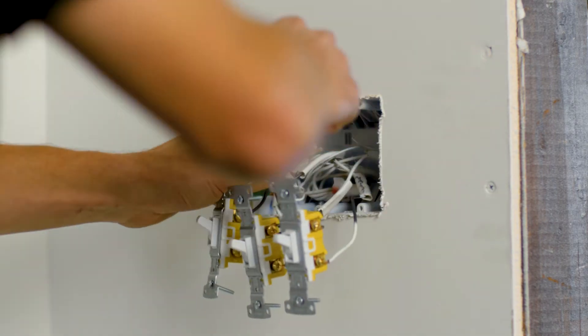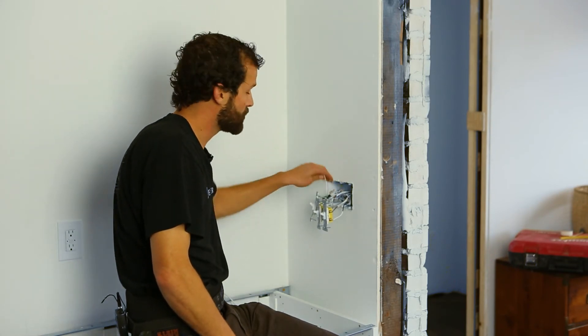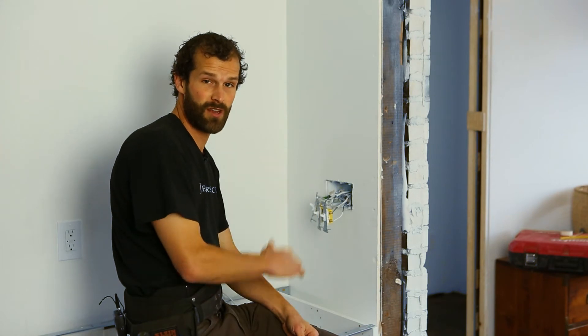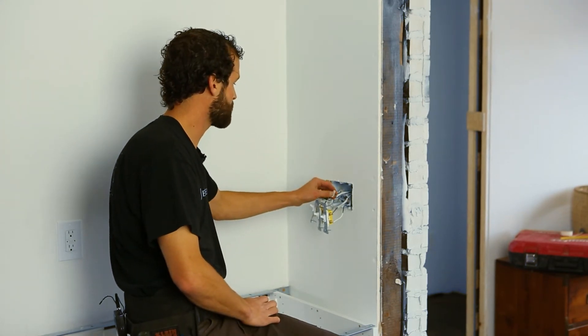What I've done there is over-tightened my wire nut or possibly I have used a wire nut that's too small for the number of conductors and size of conductors that I have. If that wire nut's under strain, sometimes spontaneously it'll fail over time.